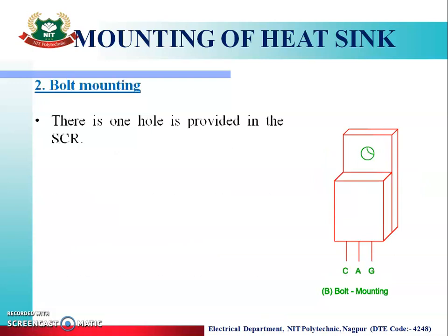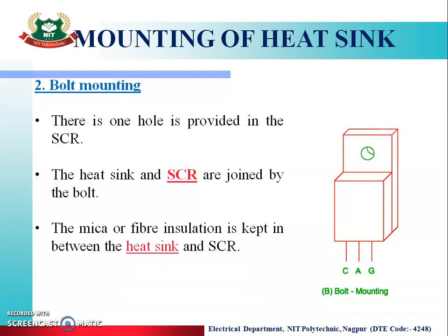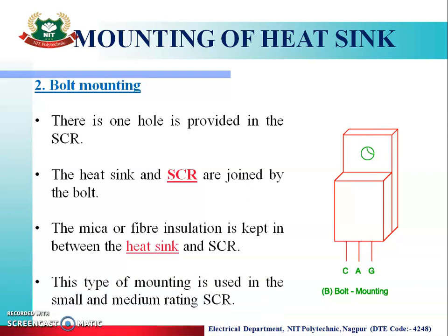The second one is the bolt mounting method. One hole is provided in the SCR so that the heat sink and the SCR are joined by the bolt. The mica and fiber insulation is kept in between the heat sink and SCR to provide electrical insulation. This type of mounting is used for small and medium rating of SCR.